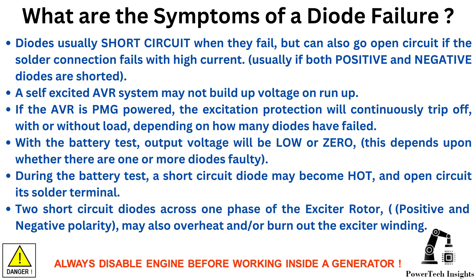With the battery test, output voltage will be low or zero — this depends on whether there are one or more diodes faulty. During the battery test, a short circuit diode may become hot, and open circuit its solder terminal. Two short circuit diodes across one phase of the exciter rotor, positive and negative polarity, may also overheat or burn out the exciter winding.